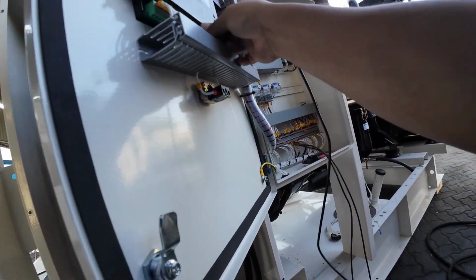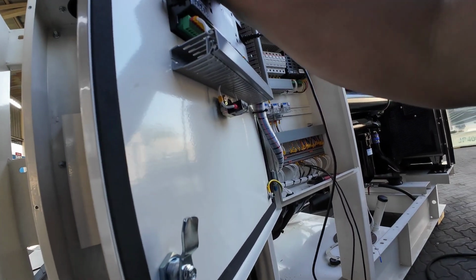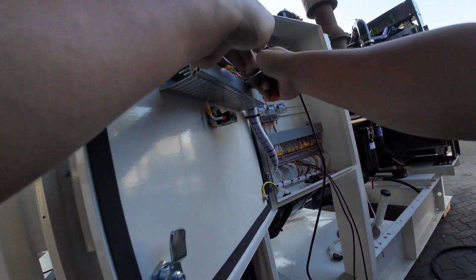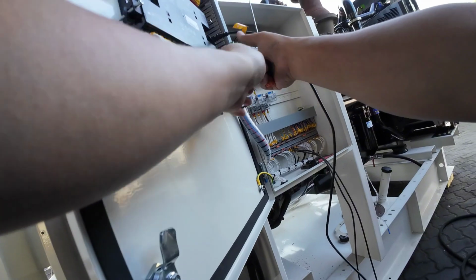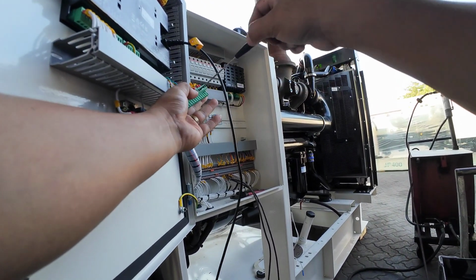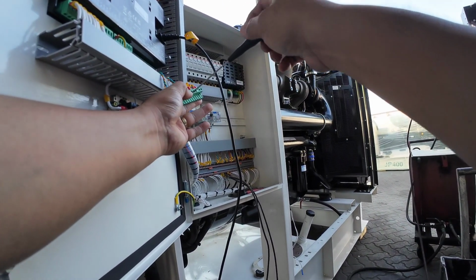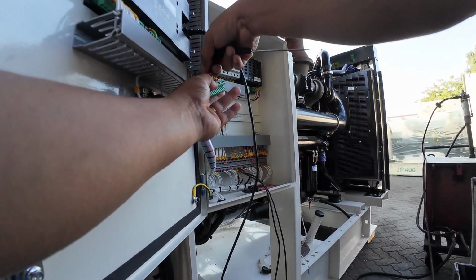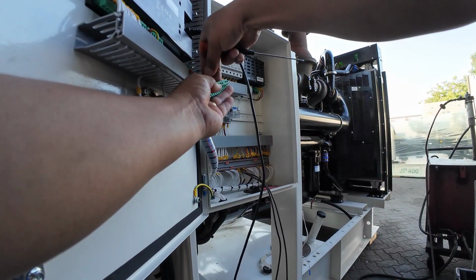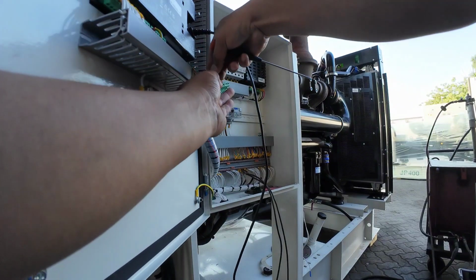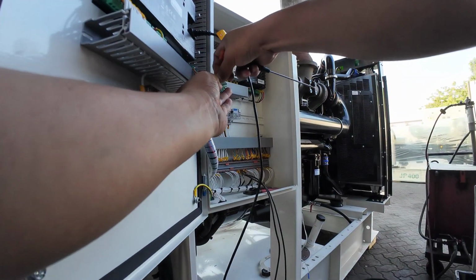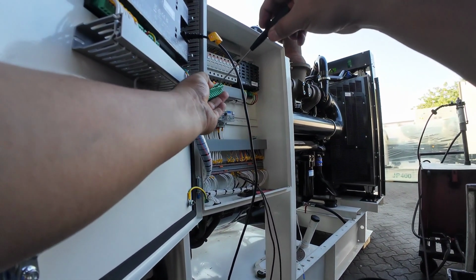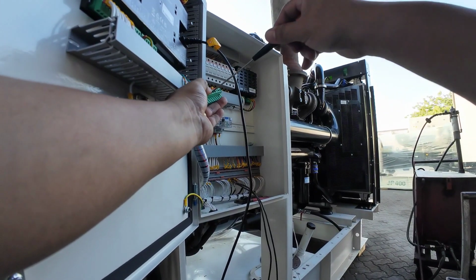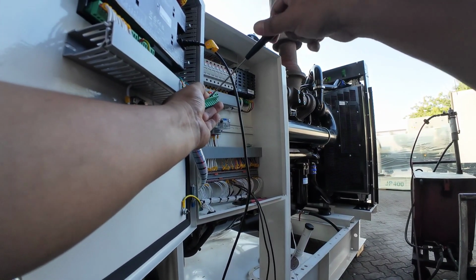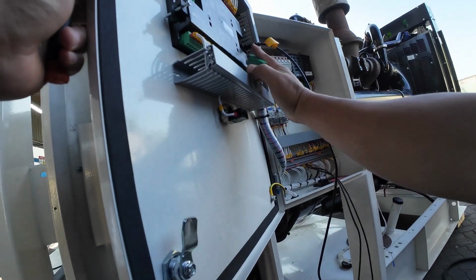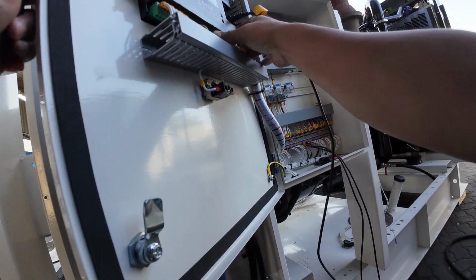In here, for the second generator, we need to do the proper calibrations as well, the same connections we need to change because we know already the connections were wrong. We need to change the wiring, and do the same calibration, configurations, and adjustment for our AVR and speed, so we can have the same level of control for this second set of generators.